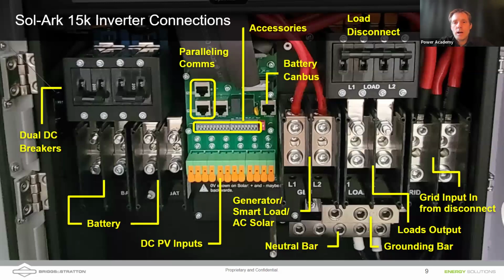As an example of the inside of an inverter, the electrical connections, we're showing a Sol-Ark 15K. You've got dual battery inputs on the left side of the inverter. And you've got DC breakers to control that, to be able to shut off essentially your battery power if you need to do servicing. And overcurrent protection there at 200 amps. We additionally have the ability to control through the accessories bars things like, as Daniel mentioned, rapid shutdown, automatic generator start. There are CT inputs there, so you can monitor power coming in from the grid. You can even monitor power coming in from the grid and use time of use settings to completely offset that, essentially limiting power by discharging the batteries.